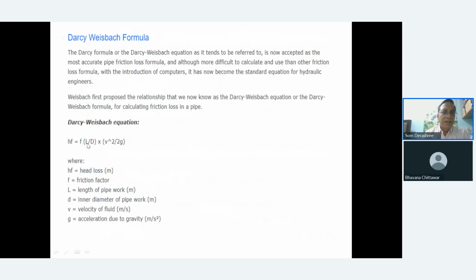A nomogram is available. L by D. Now L is the equivalent length. It is not just the length of the pipe but the equivalent length, because there will be bends, flanges, reducers and expanders, and small radius or large radius bends, etc. Velocity is known, g is known, so it will be easier to calculate the head loss. Now for F and L, let's find the equivalent length first.